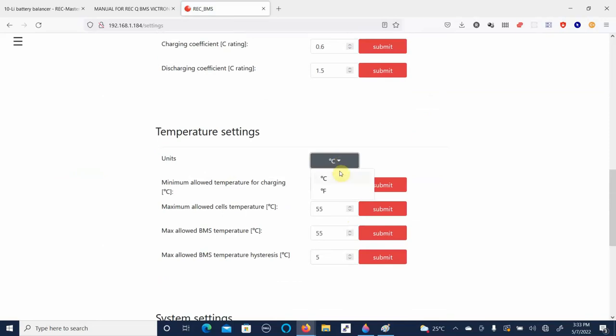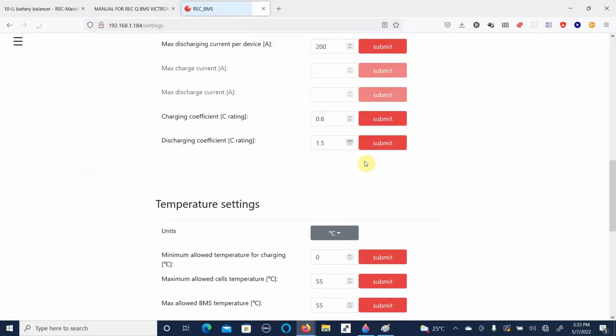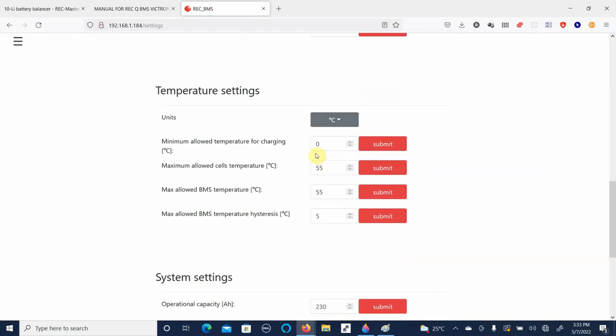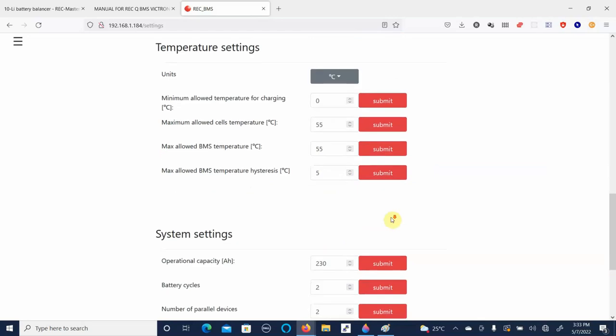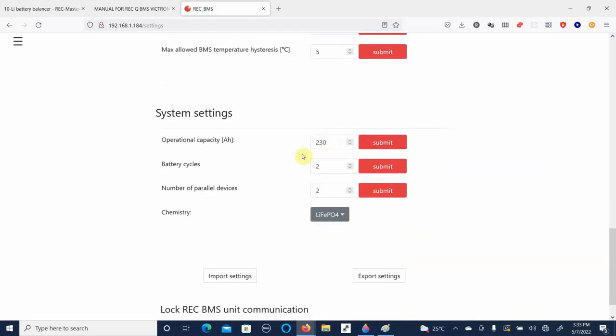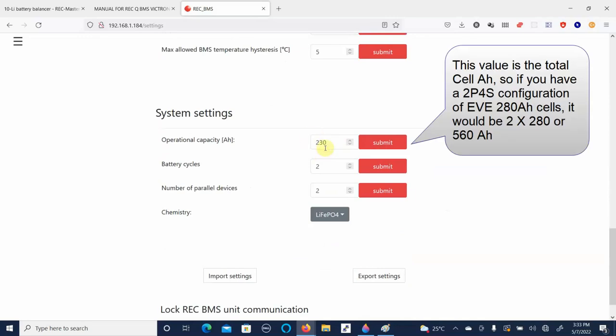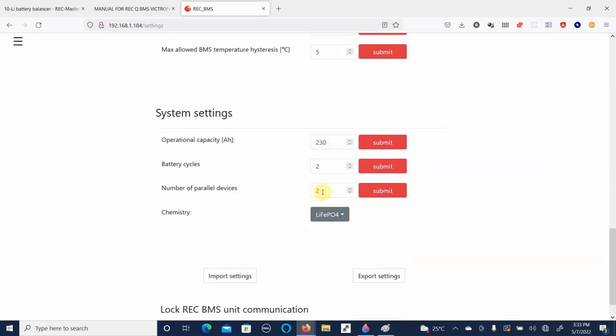We can change our engineering units from Fahrenheit to Celsius and set our minimum and maximum temperatures. Again, we really don't need to touch any of this. The only one we need to set here is how many amp hours our cells are. Now in this case I have a single cell CALB 230 amp hour, so it's just a 1P setup. So we're just going to set that at 230 amps. And we have two BMSs connected to it, two slaves. So there we set it to 2. Chemistry here is LiFePO4.